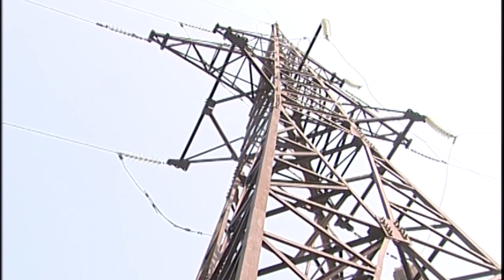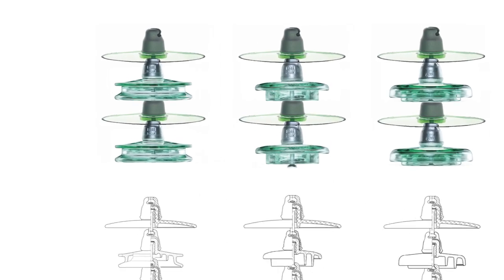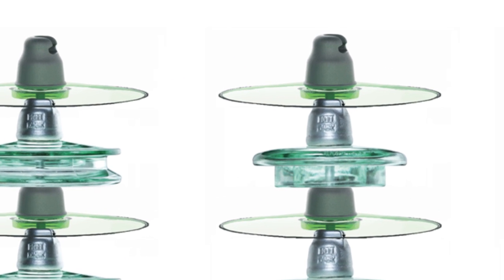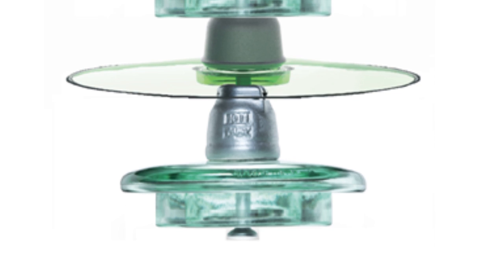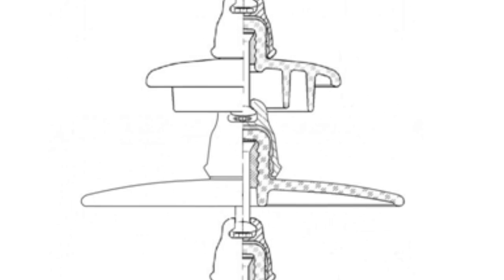We may influence the waterproof quality of insulation, the design characteristics of a string, and the design of the glass part. An aerodynamic profile is designed for easy air blow-off to prevent dust fall and is easily self-cleaned by wind and rain — good for dry dust deposits with a large creepage distance. Fog-type insulators with extended ribs also have a large creepage distance and are designed to prevent moist liquid contaminations. Global Insulator Group offers the use of mixed-type strings combining aerodynamic and fog profile qualities, allowing increased ability to withstand composite pollutions by interchanging insulator profiles with horizontal and vertical ribs.